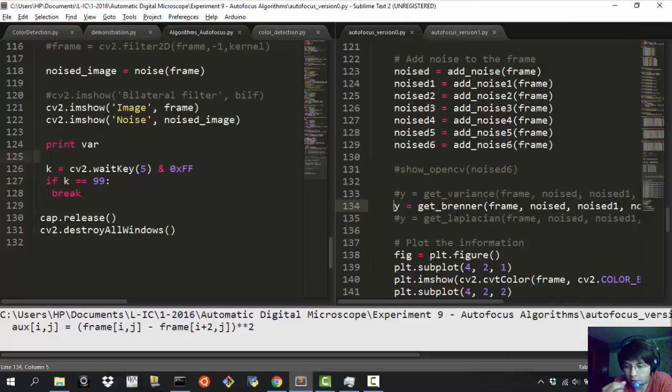So if you have seen the videos about the automatic digital microscope, in the z-axis we have added a button. So whenever the z-axis goes up, it gets to a point where it touches the sensor, and the sensor tells that it is the home starting point for the z-axis. So we know where that is. We have calculated it with a vernier. So from there we just have to go down 1 or 2 millimeters, and from there we have a not so huge function to calculate our focus.